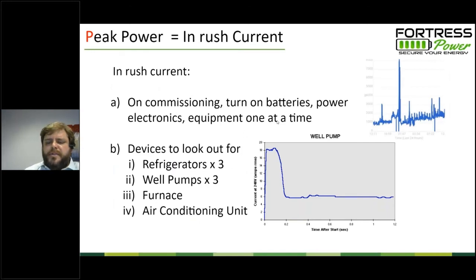And so there's another kind of inrush current. Yes, some loads, some well pumps, have incredible inrush currents that are 3 to 5 times their normal operating load. And that means if you have a motor like a well pump, you look at it and it's only supposed to be running at 2 kW, it might have a 6 kW or 8 kW startup load, and you need to make sure your battery is capable of supplying that as well as your inverter, for that matter. You also have what might be called inrush currents because it's not really continuous output capacity, but I would call them short duration loads. Loads that are measured in minutes rather than seconds, that you also have to be aware of or on the lookout for.